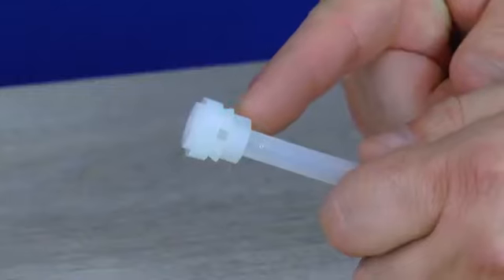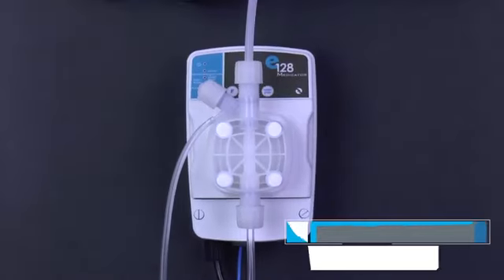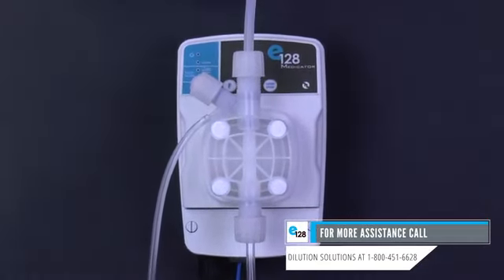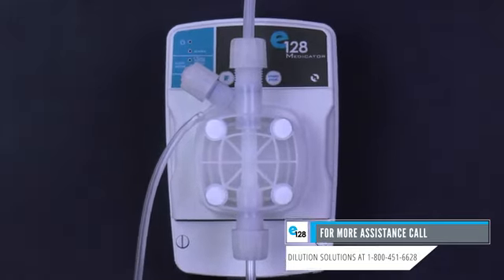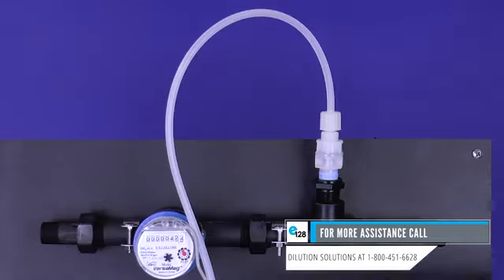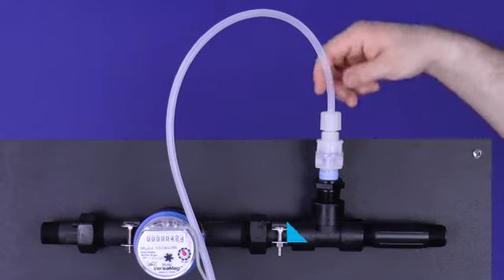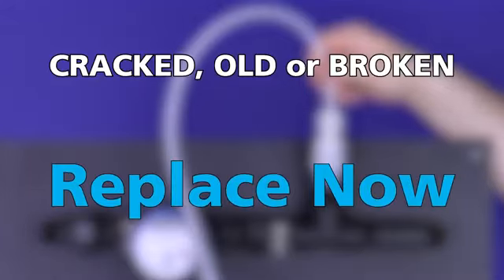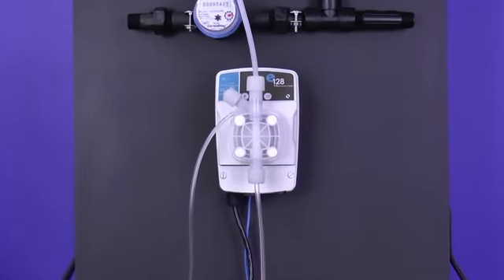Tube condition. Always be mindful of the orientation for the tubing connections. This is key because without the proper orientation, it can allow air into the system, causing the E128 to not operate correctly. To finish up, look at the rigid discharge tube's condition. If the tube's cracked, rigid, or looks really old, just replace it now. The E128 should now be properly injecting.